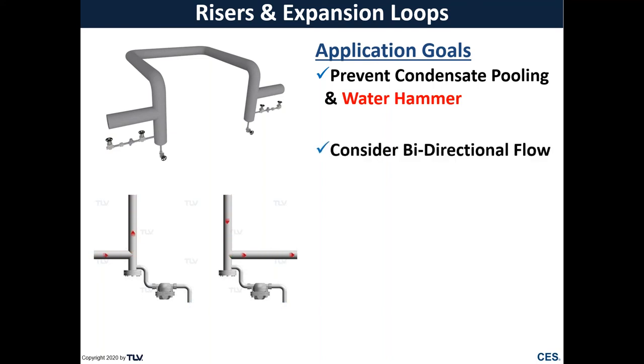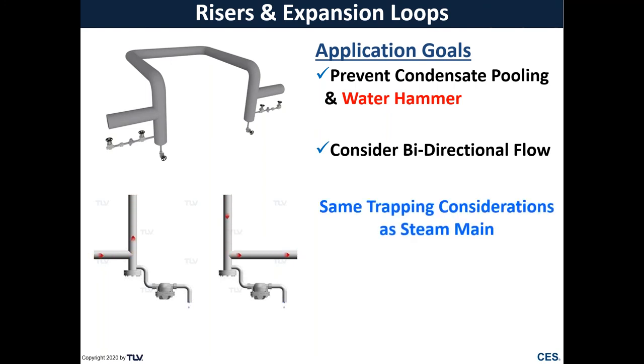One thing we need to consider is bidirectional flow. In larger steam systems, we may have multiple steam generation points, so we could see flow in both directions along this pipeline, depending on operation. So we need to make sure that we have traps upstream and downstream of these expansion loops. And again, our trapping considerations are the same as for a typical drip trap on a steam main.